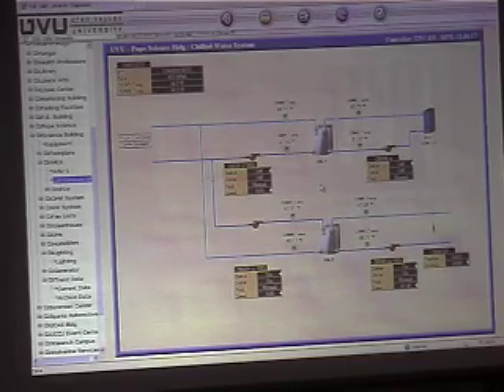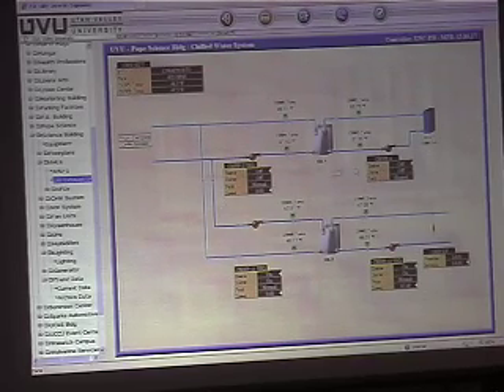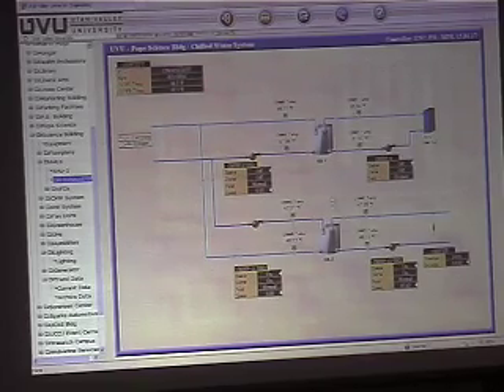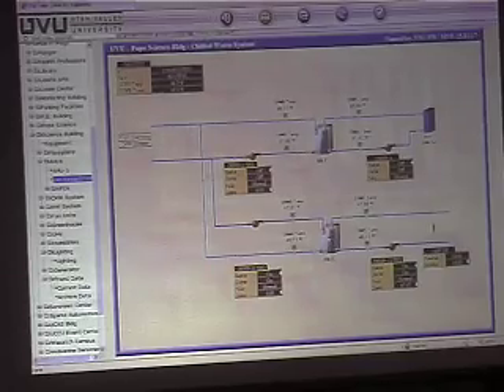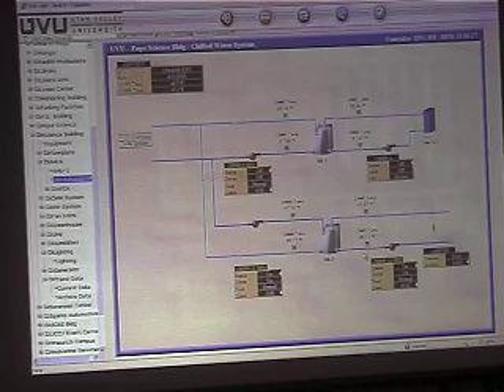Whenever there's a call for cooling off of this coil, based off of the discharge air of the air handler, both of these pumps will kick on. This one here is on a VFD, so it'll modulate its speed to control the discharge temp. The other one's just constant volume. This heat exchanger here serves your process control equipment that's in the building that requires a cooling system.